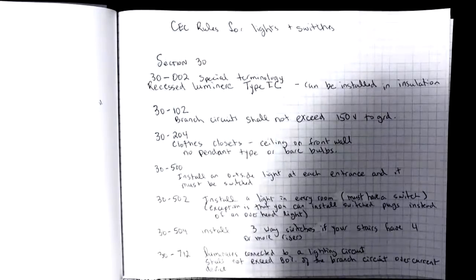30-204, when we're installing a light in a closet, we have to be really careful with the position of that light. We're allowed to put them on the ceiling, often they're on the front wall just above the door. You're not allowed to use a pendant type or have bare bulbs. You're just worried about that heat from the incandescent bulbs getting too close to your clothes and causing a fire.